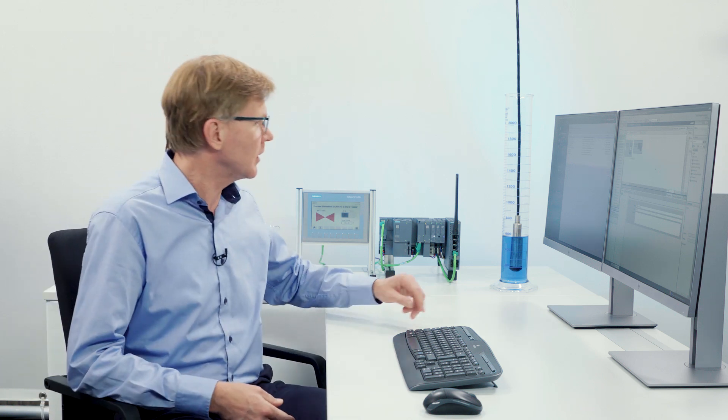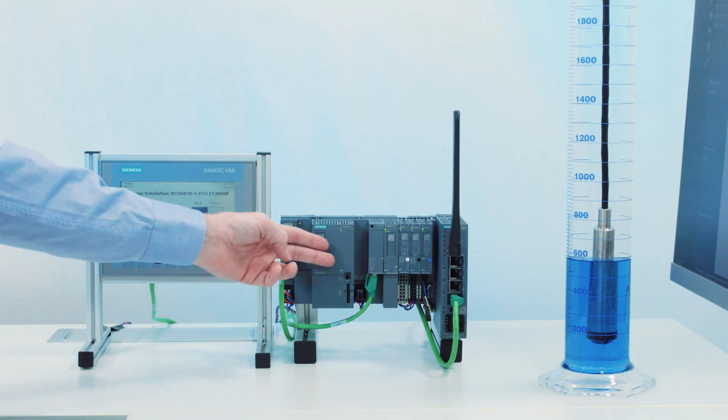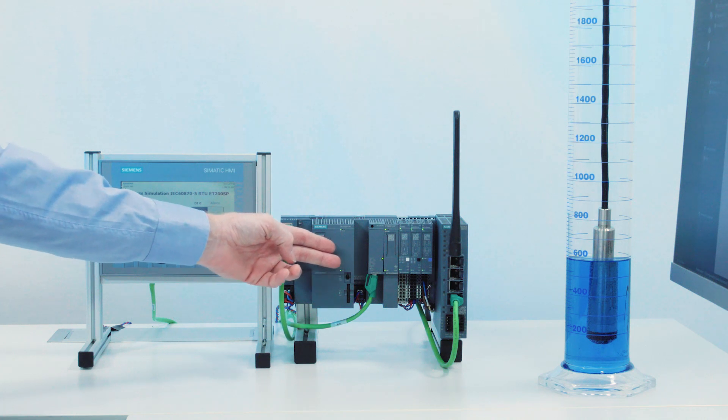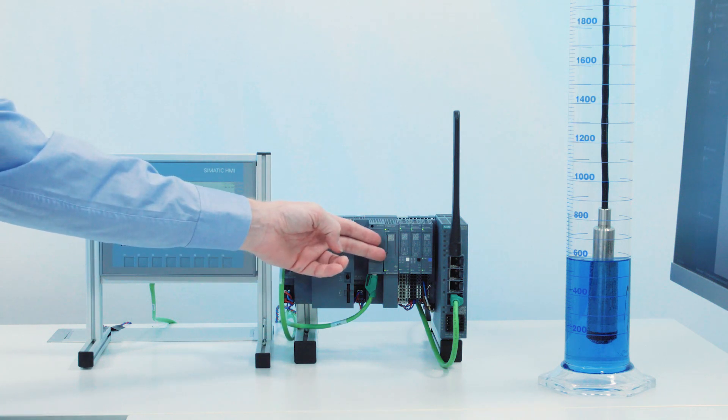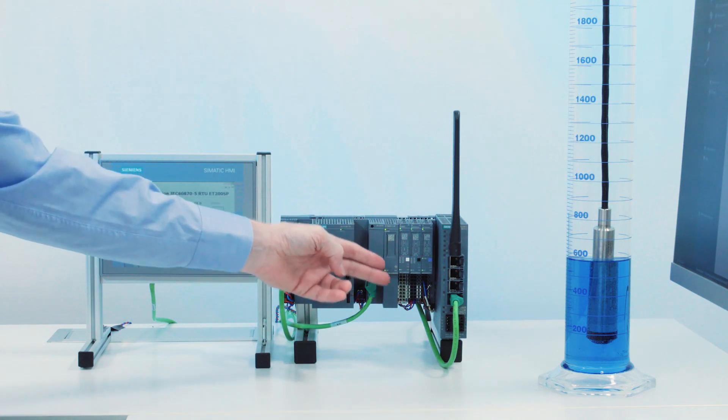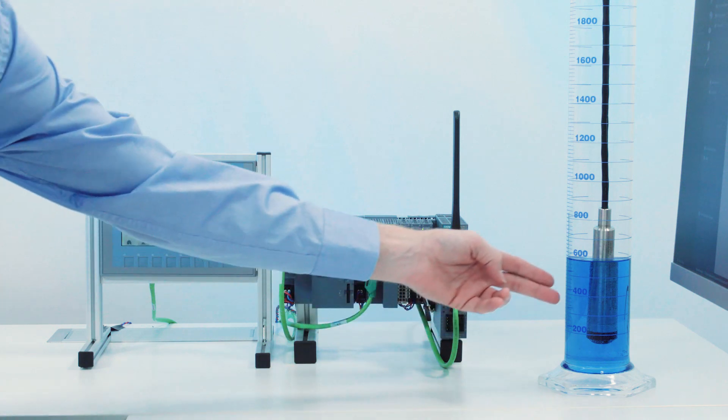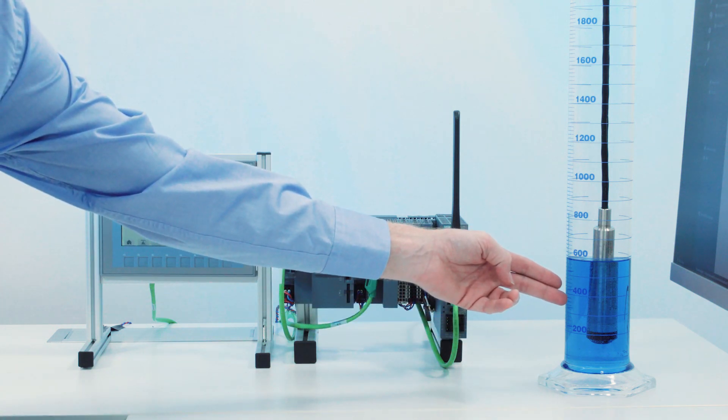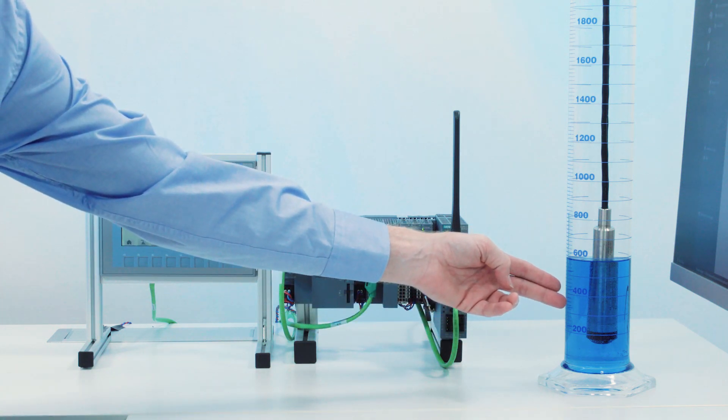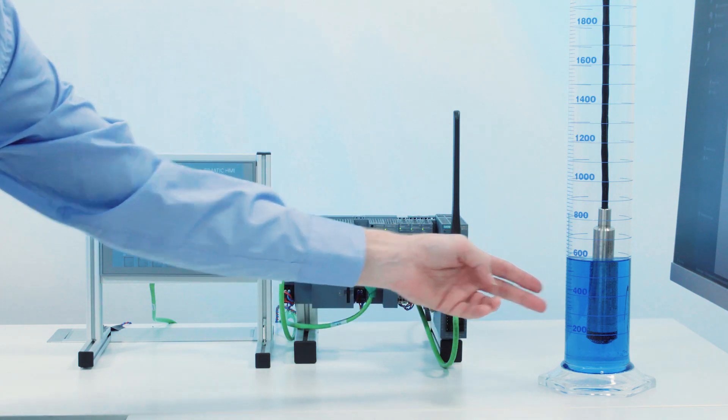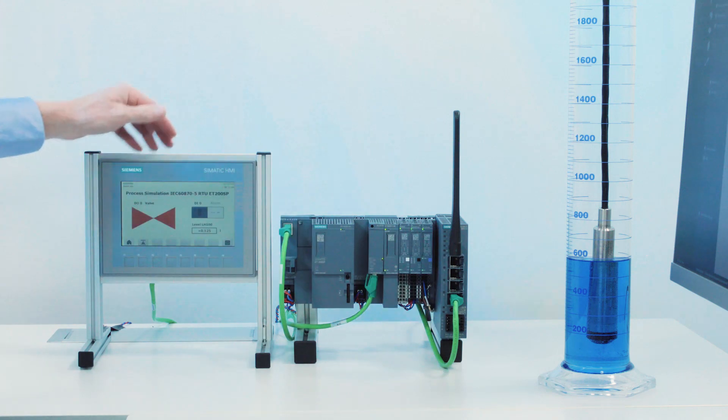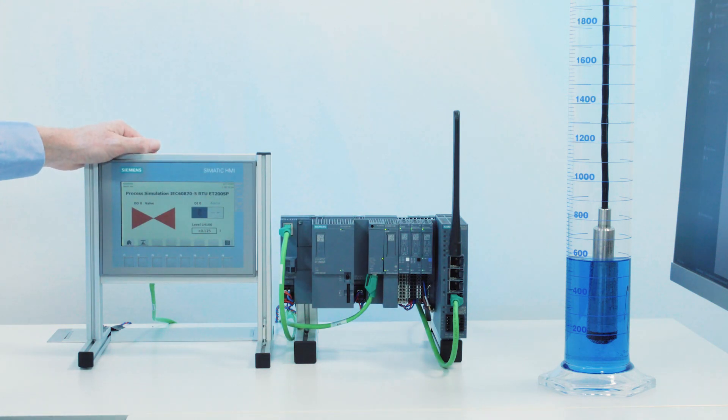In the next 10 minutes, I will demonstrate how easy it is to configure and commission an RTU with IEC 60870-5 protocol. I will use a distributed controller SIMATIC ET200SP and a CP1542SP-1 IRC. The CPU acquires a measured value from the level sensor SITRANS LH100. In addition, it controls a valve. The valve is simulated on the panel.